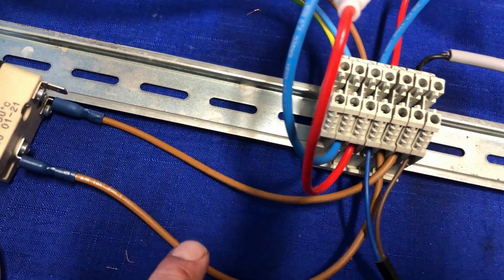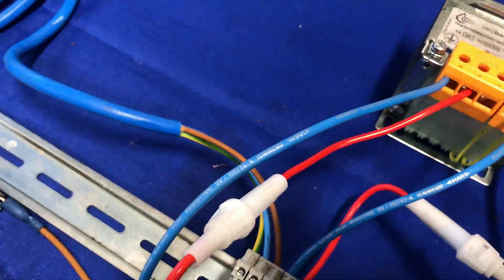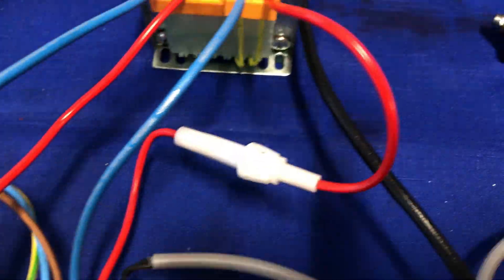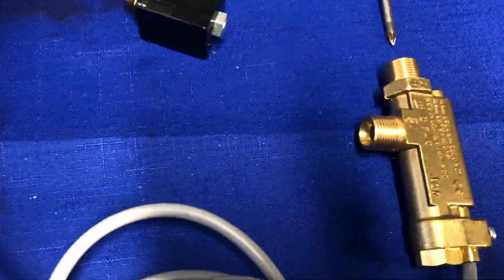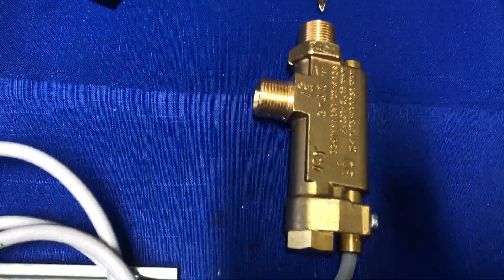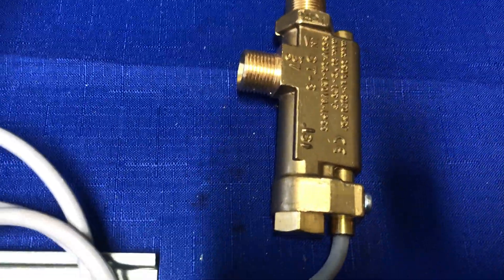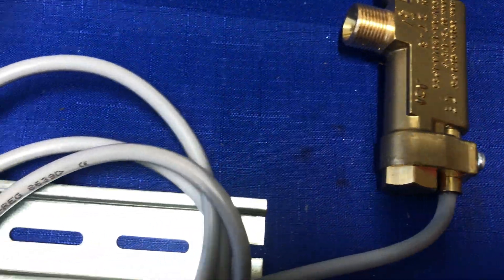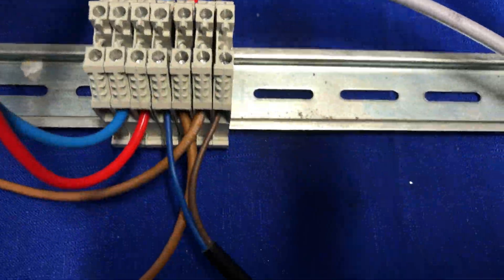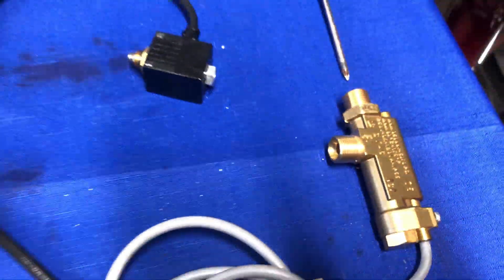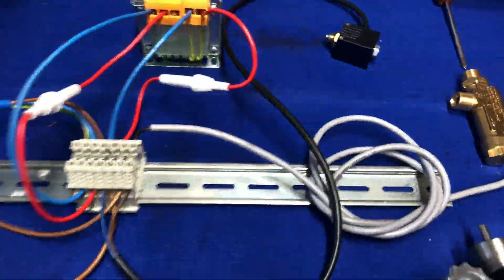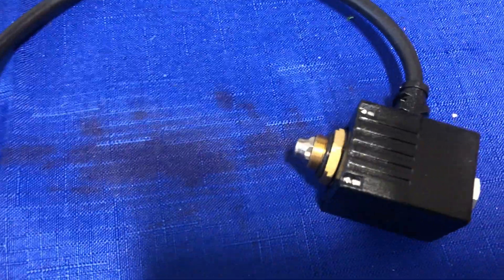As shown before, you've got 24 volt going in, 24 volt coming out, and that goes to the fuel solenoid. If we push this in now, the magnetizing on the coil pulls it in.